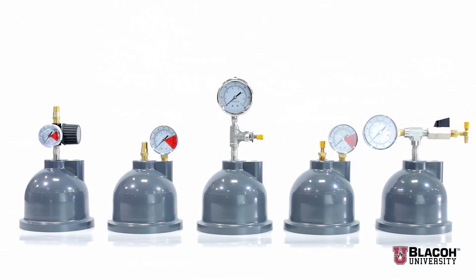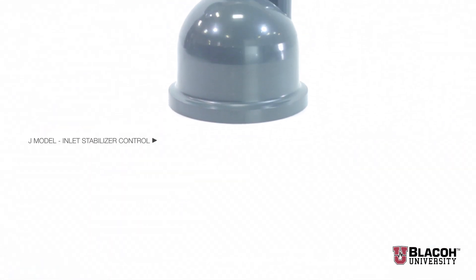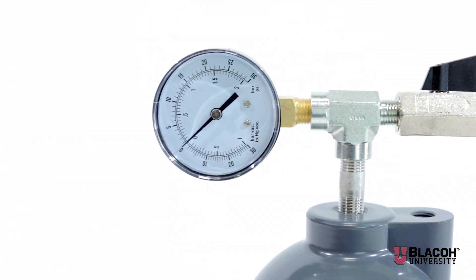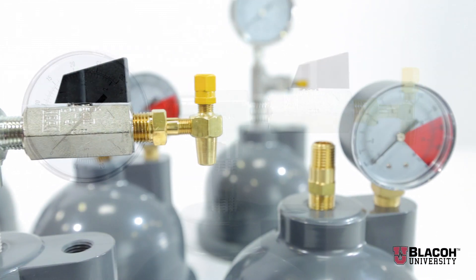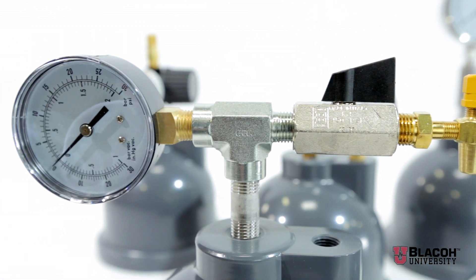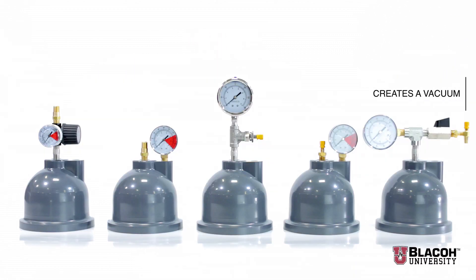The fourth model that Blacoh makes is called the J model or inlet stabilizer control. It consists of a compound gauge which shows both vacuum and pressure, an air-type check valve, and a venturi valve. This design is unique and patented by Blacoh. When the application is a suction lift situation, applying compressed air to one end of the venturi valve creates rapidly flowing air which draws pressure out of the air side of the dampener and creates a vacuum.